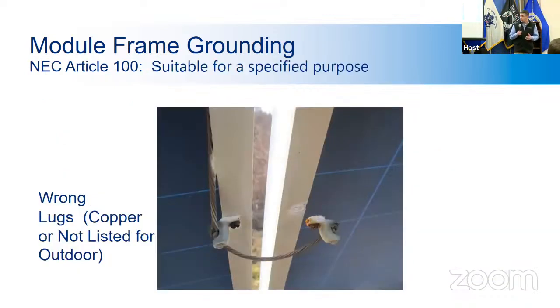All right, so here we have a situation where a contractor used, I believe, copper grounding lugs with aluminum frames, sorry, on the panels. What we have here is corrosion due to different metals being in contact. As you can see, this is not going to be code compliant because the grounding lug is completely removed from the panel. And this can happen extremely quickly. This happened between installation and when the inspection took place. The screw had already corroded to a point where it snapped off and completely disconnected from the panel. So if you don't use weather rated equipment, it can cause issues very quickly.